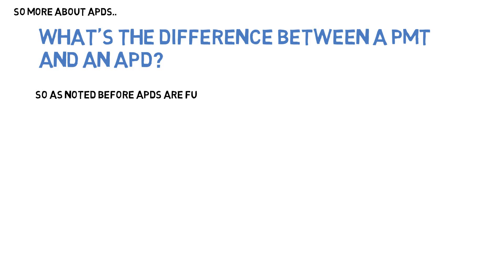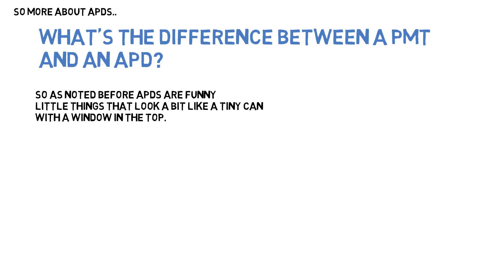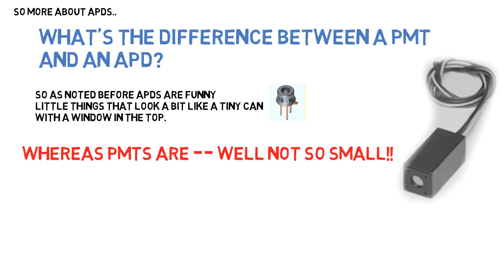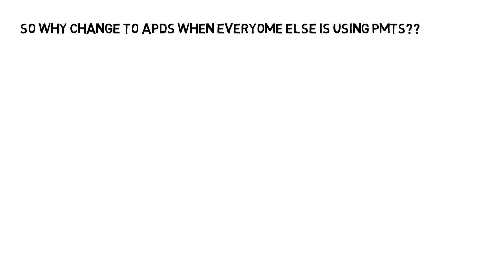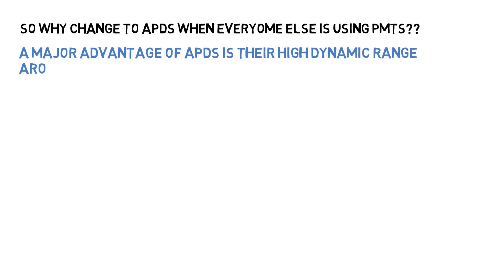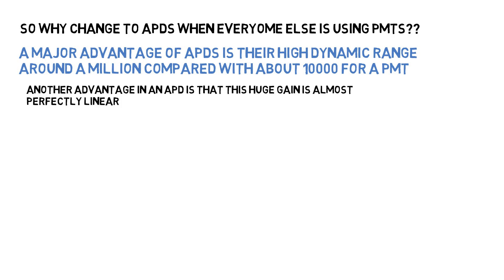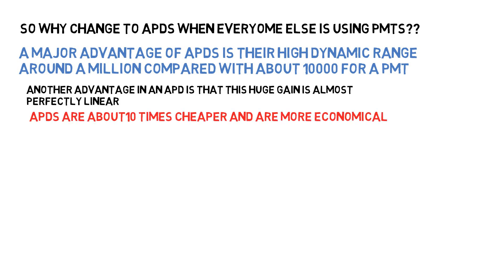What's the fundamental difference between a PMT and an APD? APDs are very small devices, often looking like a tin can with a window on the top, whereas PMTs are much bigger. A major advantage of APDs is their high dynamic range — about a million compared to about 10,000 for a PMT. Another advantage is that this huge gain is almost perfectly linear. APDs are about 10 times cheaper, maybe more, and are more economical.